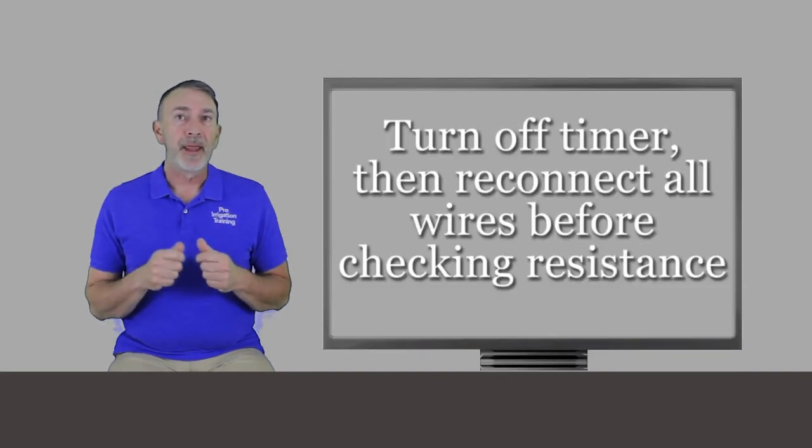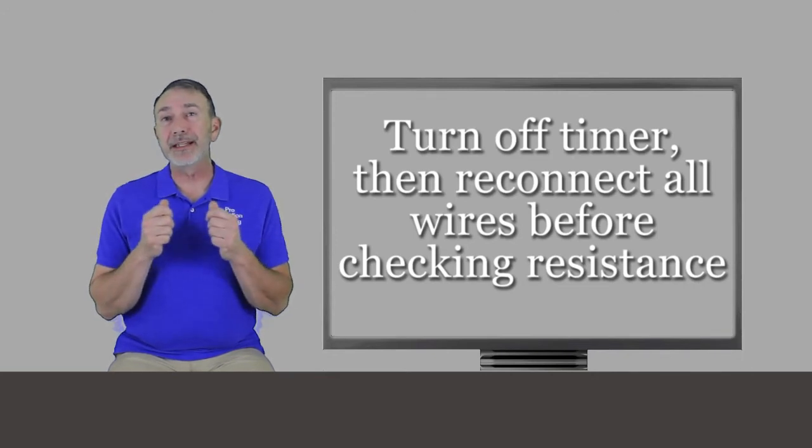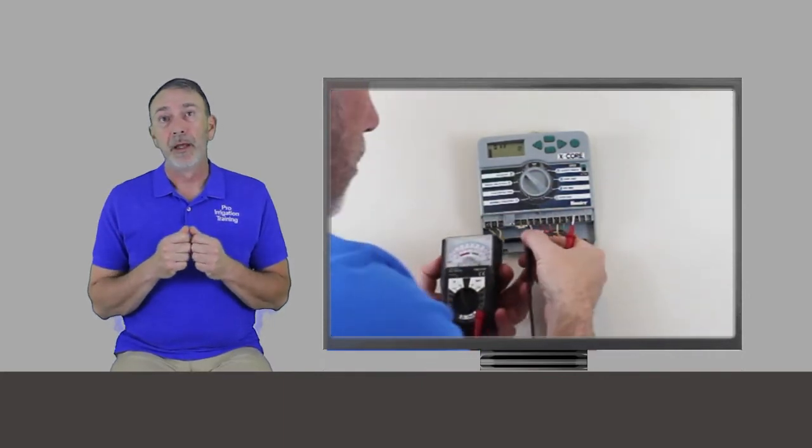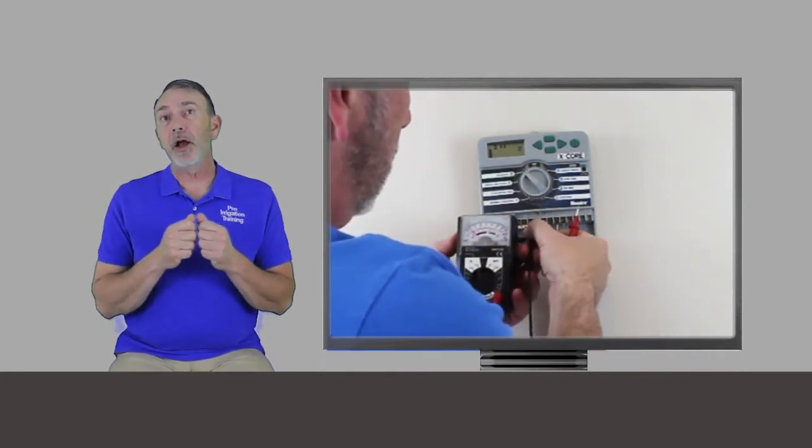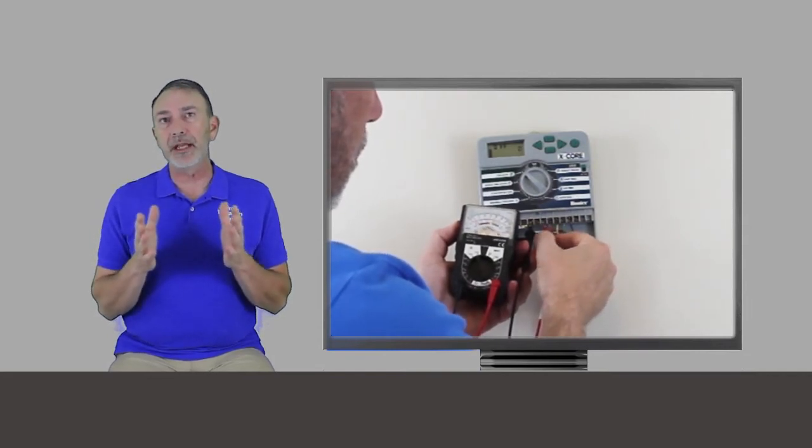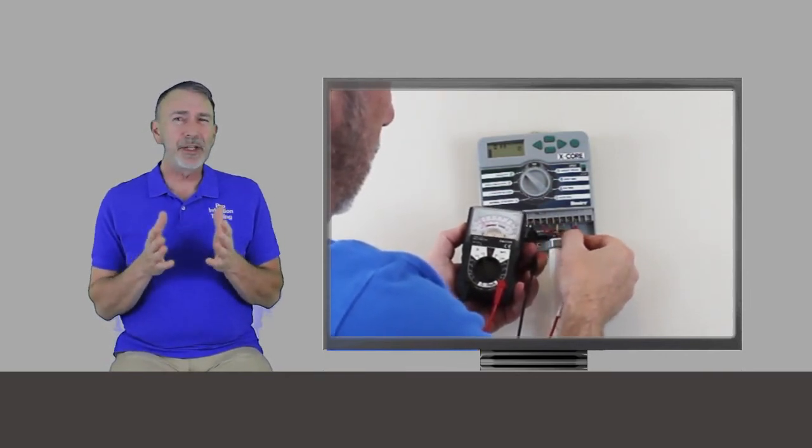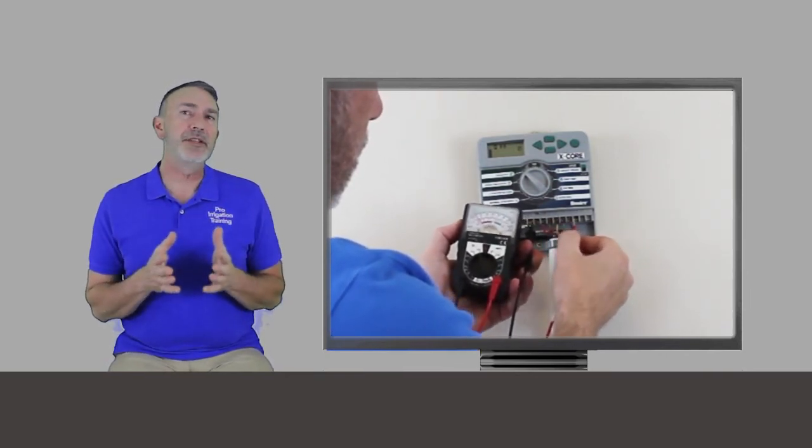Now, assuming that all the voltage checks are okay, turn off your timer, ensure there's no current flowing, and now let's check the resistance of that circuit in question with our ohm setting on our multimeter. Also check all the other zone circuits at this time to try to get an idea of what the normal resistance reading is going to look like from all of our other ostensibly operational zone circuits. It helps to know what kind of valves that you've got on the system so that you can know how many ohms to expect from a healthy operational solenoid.